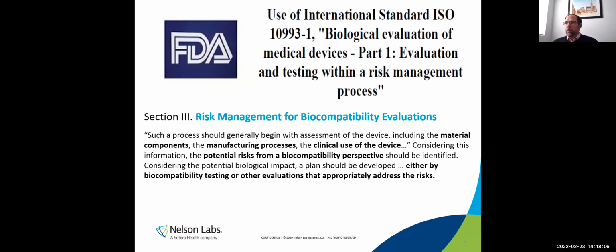So those are the two inputs we always add to our risk assessments when you're looking at a change. The other thing that I wanted to throw up here is that, so this is right out of the FDA's guidance document on how to use 10993-1. And it also has a risk-based approach. And in this, it spells out, I think it's a great formula on how to do your risk assessment.